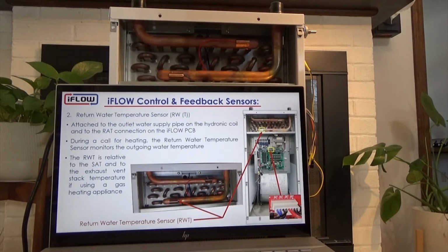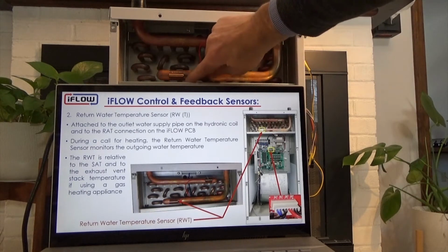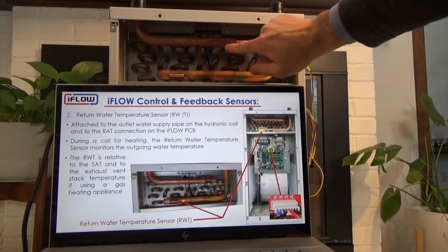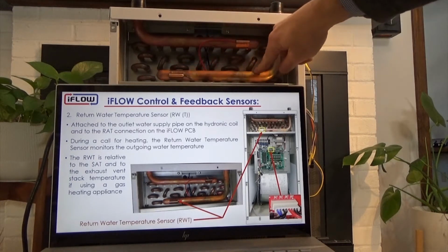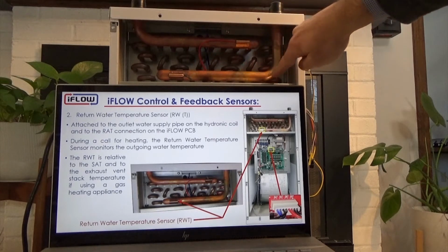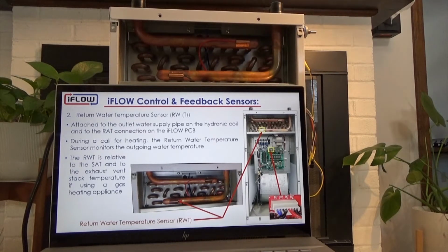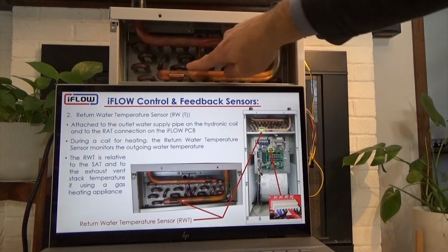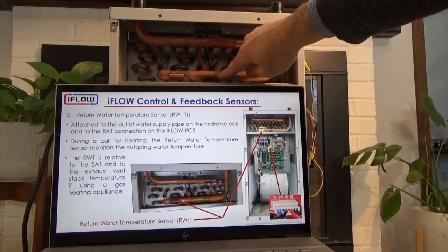The return water temperature sensor is basically this black wire with the copper sensor, and that is connected to the return pipe. As the water leaves the hydronic coil and goes back to the heat source for reheating, it makes up part of the team that gives us the delta T.